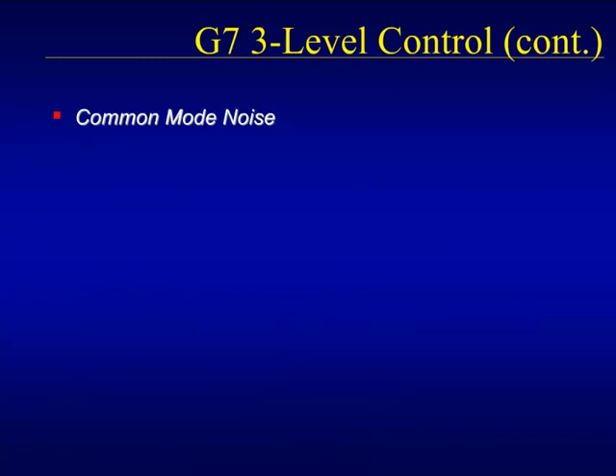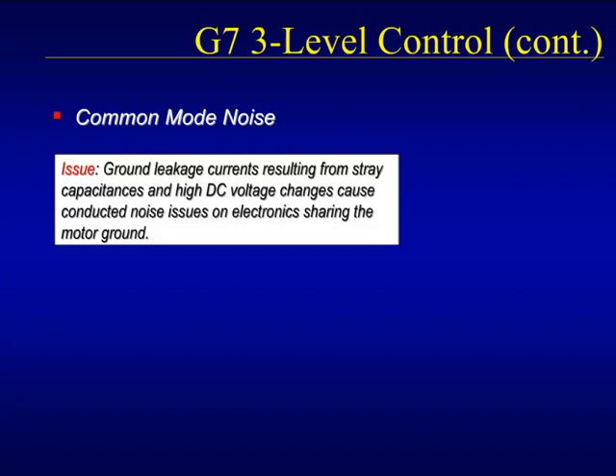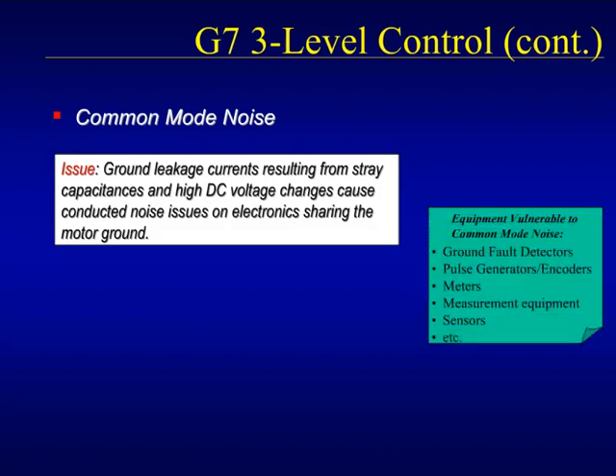Capacitive coupling again plays a role in another potential problem caused by common mode voltages. Capacitive coupling between the ground and the motor leads will cause leakage currents to be induced on the ground lead. This noise caused by the leakage current may disrupt the operation of sensitive equipment that uses the same grounding point as the motor and drive.